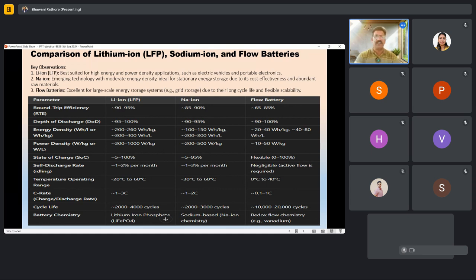Next is C rate, 1 to 3C. If 1C means a 100 ampere hour battery, giving 100 amperes for 1 hour will charge or discharge it. Up to 3C is fast charging and discharging. For sodium ion it is 1 to 2C, but for flow batteries we cannot fast charge or discharge, only 0.1 to 1C. Cycle life: LFP battery 2000 to 4000 cycles, sodium ion 2000 to 3000, and flow battery is best, 10,000 to 20,000 cycles with no impact.